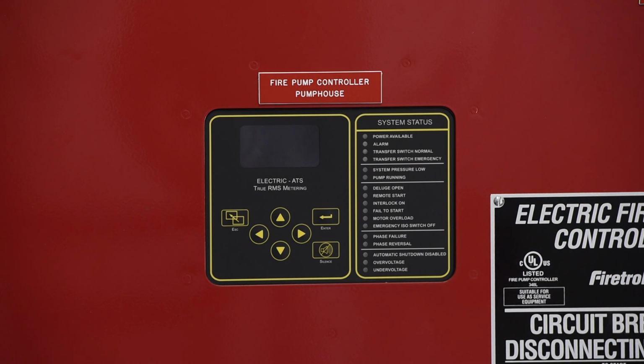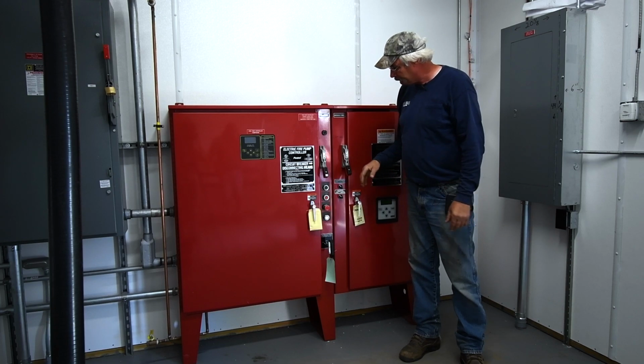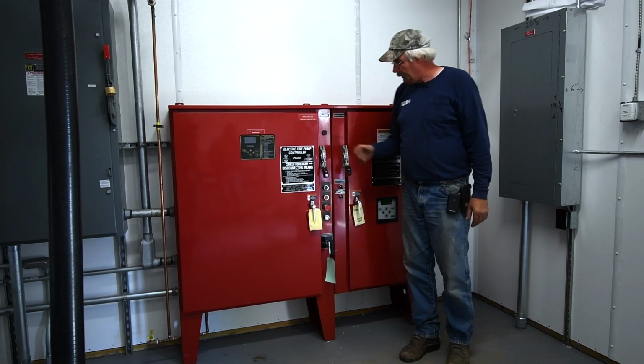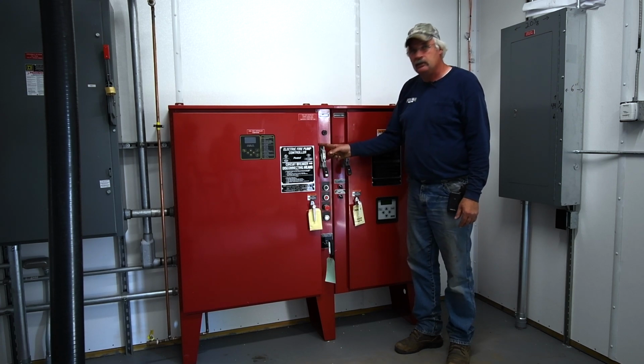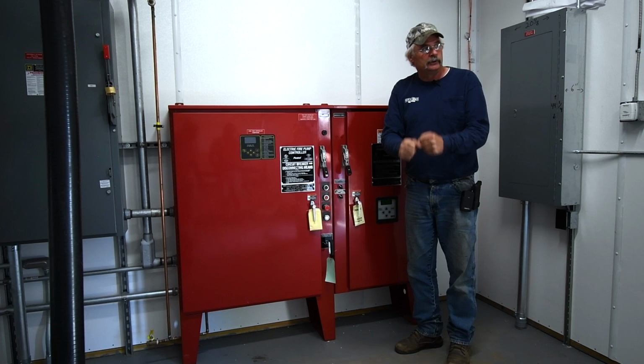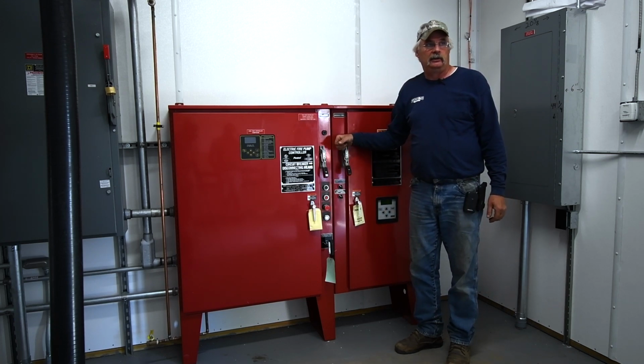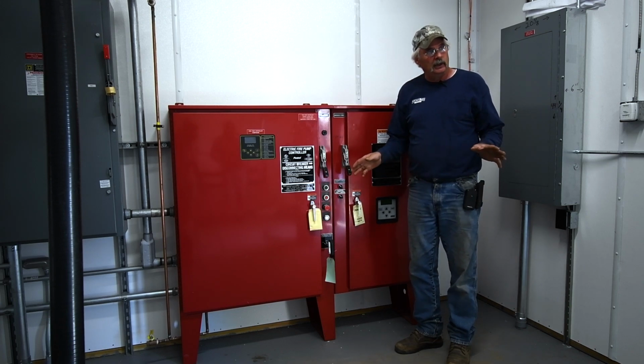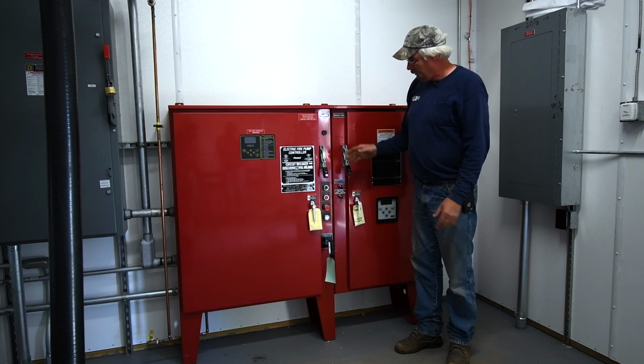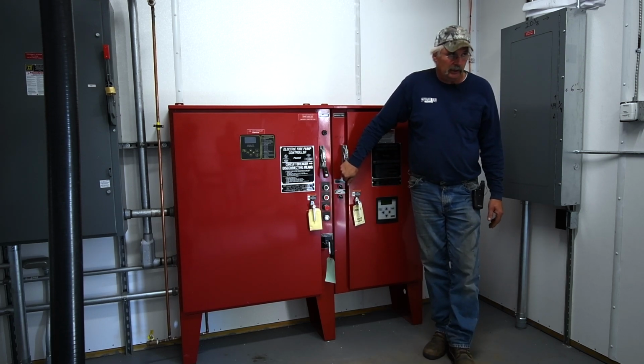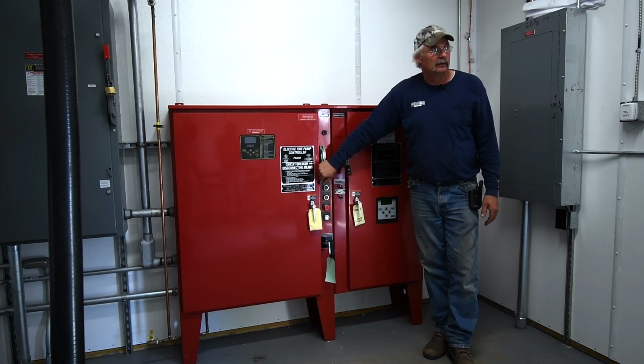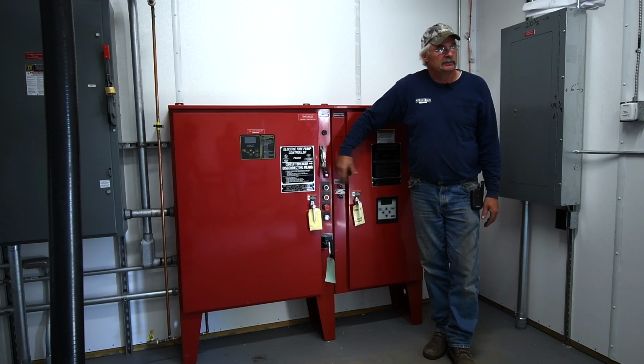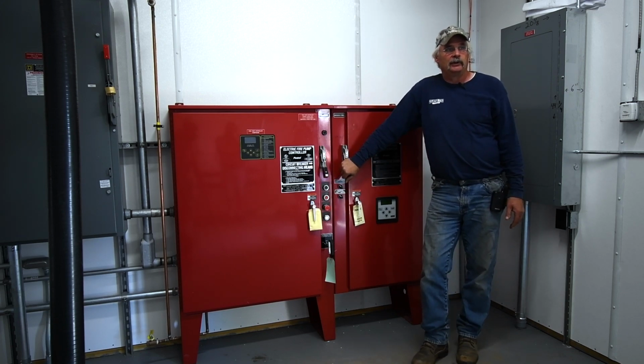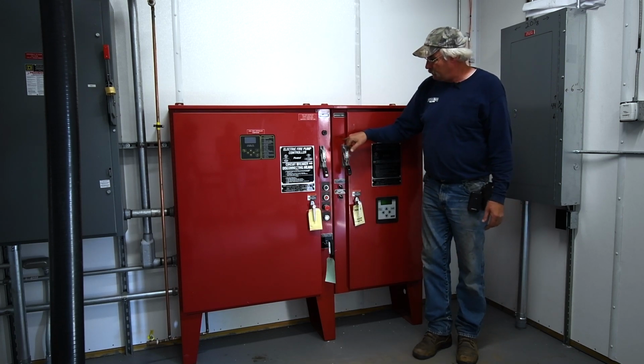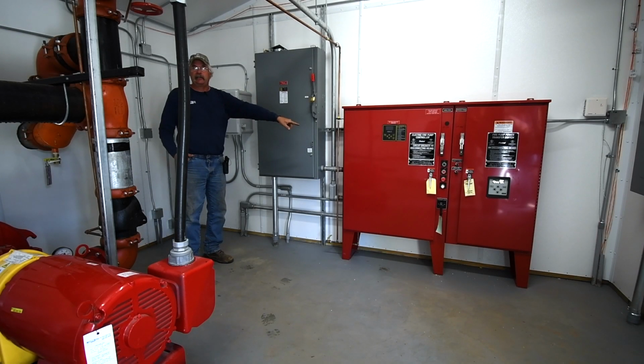This is set up to run normally on AC power, which is from your power company. And both of these levers will be up. Now, if you shut your AC power off, it's going to be like the power company turned your power off. Your diesel generator will kick on immediately. So if you want to shut these cabinets off, do any maintenance work, any wiring, anything like that, you have to shut the DC power, the generator, off first, and then your AC power. Because your AC switch is monitored. These two are watching each other. If you shut one off before the other one, the generator will kick on. And that's why we've got first off, first on. This is just our main power coming in for our AC there.